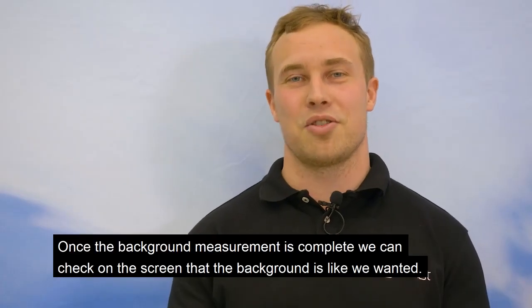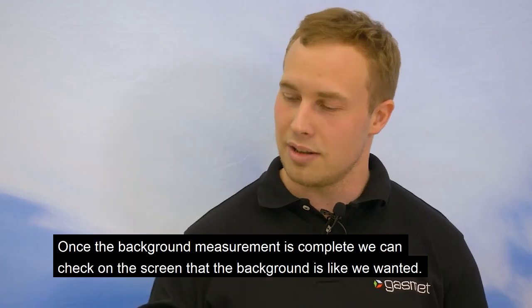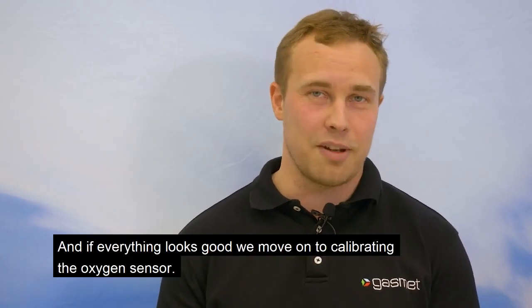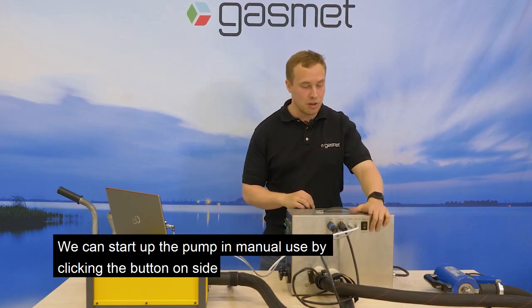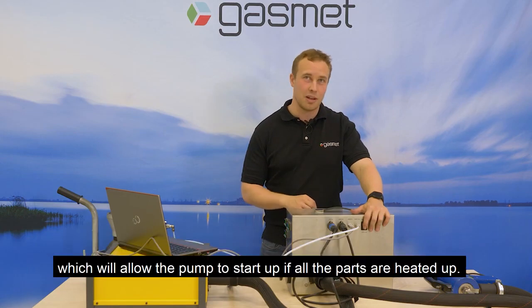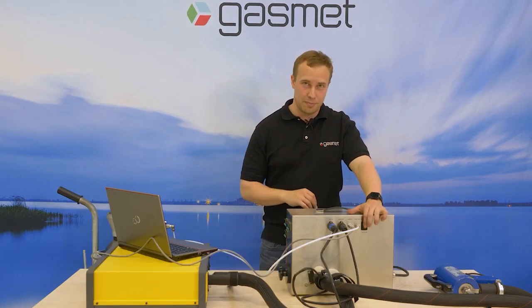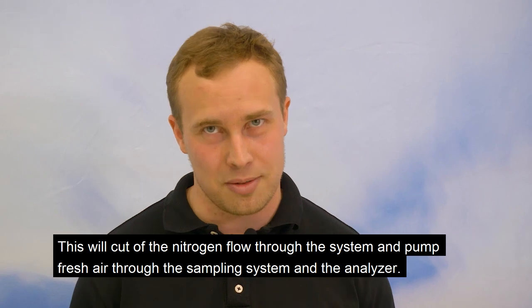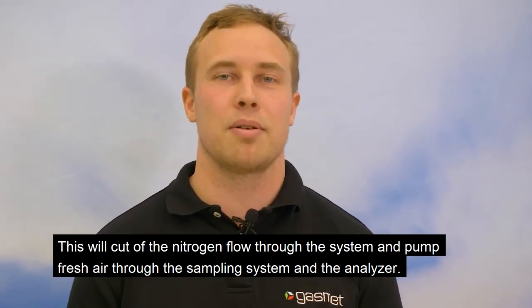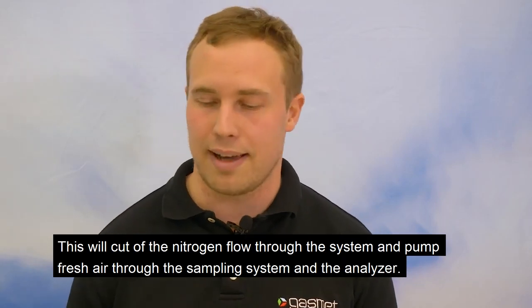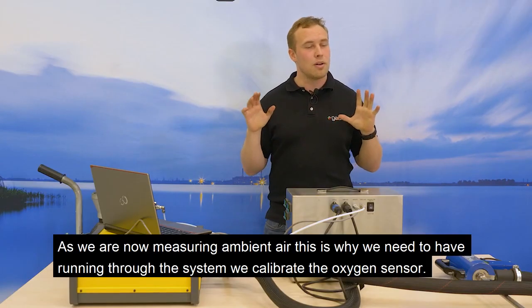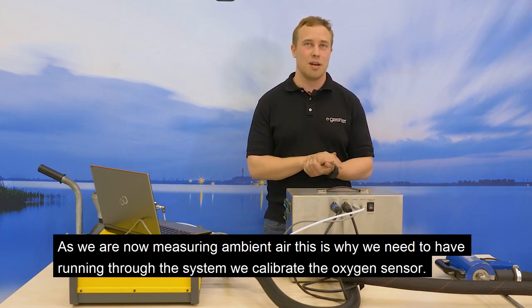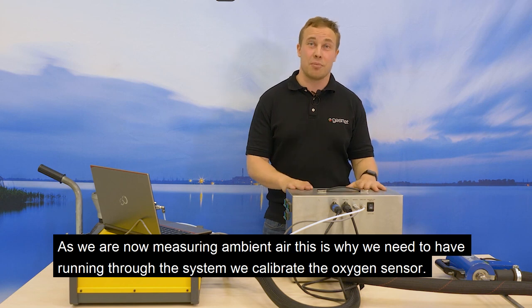Once the background measurement is complete, we can check on the screen that the background is like we want it, and if everything looks good, we move on to calibrating the oxygen sensor. We can start up the pump in manual use by clicking the button on the side, which will allow the pump to start up if all the parts are heated up. This will cut off the nitrogen flow through the system and pump fresh air through the sampling system and the analyzer. As we are now measuring ambient air, this is what we need to have running to the system when we calibrate the oxygen sensor.